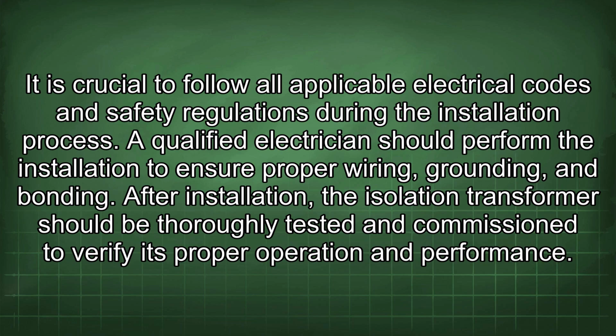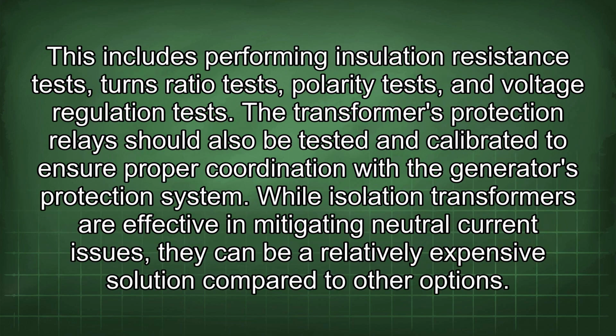After installation, the isolation transformer should be thoroughly tested and commissioned to verify its proper operation and performance. This includes performing insulation resistance tests, turns ratio tests, polarity tests, and voltage regulation tests. The transformer's protection relays should also be tested and calibrated to ensure proper coordination with the generator's protection system.